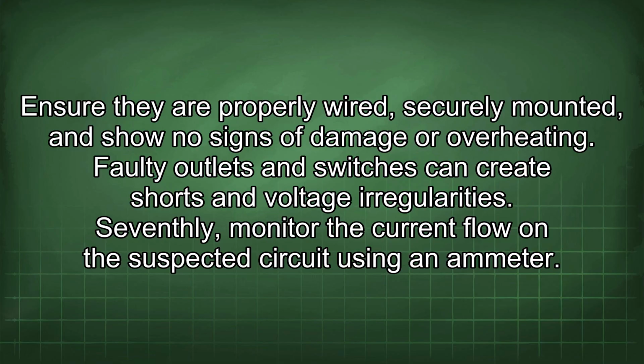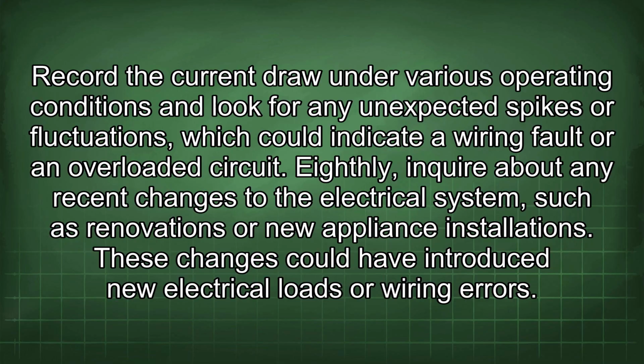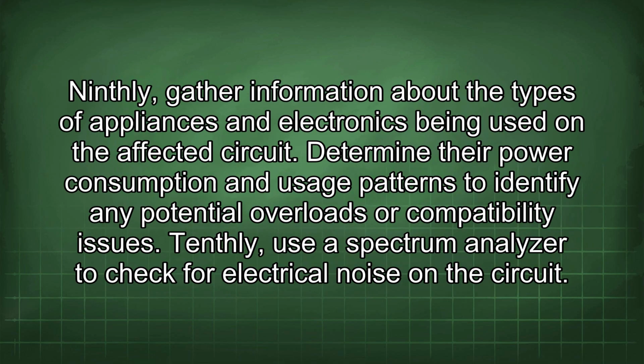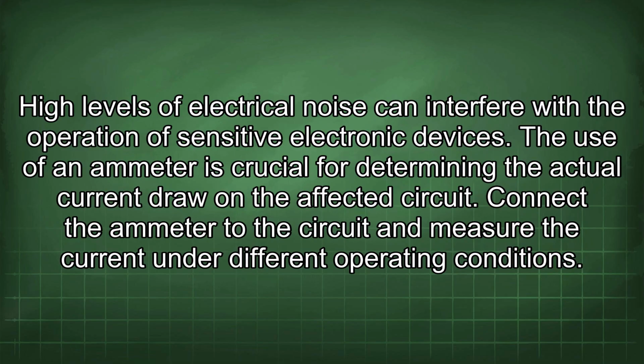Seventhly, monitor the current flow on the suspected circuit using an ammeter. Record the current draw under various operating conditions and look for any unexpected spikes or fluctuations which could indicate a wiring fault or an overloaded circuit. Eighthly, inquire about any recent changes to the electrical system such as renovations or new appliance installations. These changes could have introduced new electrical loads or wiring errors. Ninthly, gather information about the types of appliances and electronics being used in the affected circuit. Determine their power consumption and usage patterns to identify any potential overloads or compatibility issues. Tenthly, use a spectrum analyzer to check for electrical noise on the circuit. High levels of electrical noise can interfere with the operation of sensitive electronic devices.